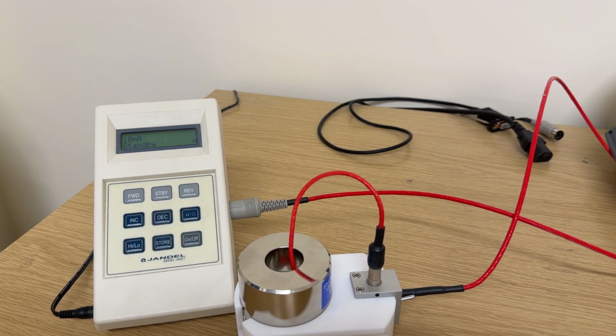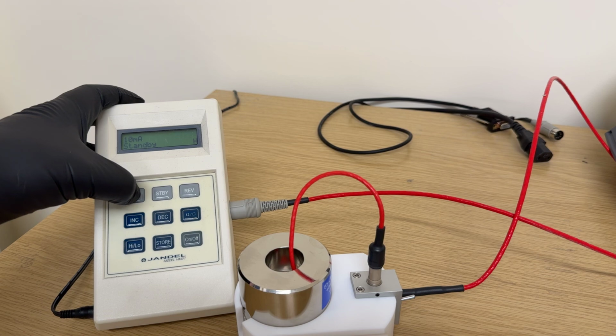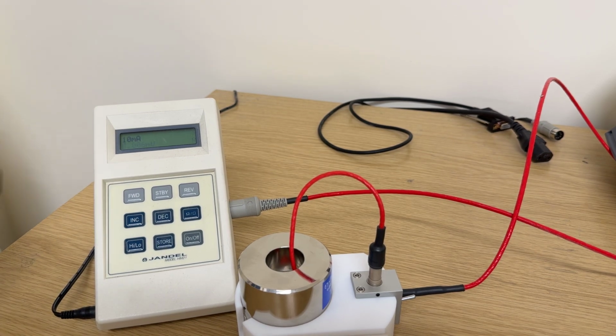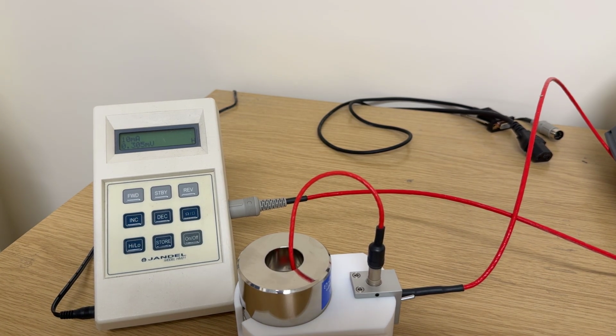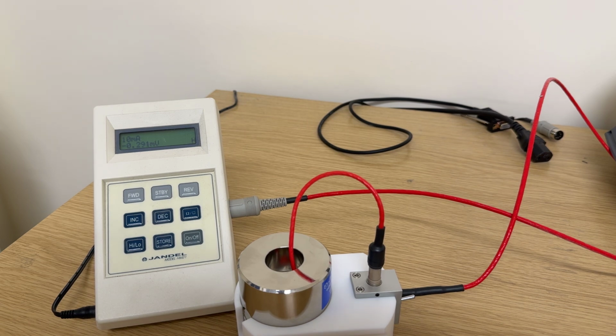And the HM21 here is on 10 milliamps, which is its highest current. We needed 100 milliamps really with the RM3000 Plus. So instead of getting 3 millivolts, we'll expect around 0.3 millivolts. So we're coming down towards the limits of measurement of the HM21. I'll pass the current in the forward direction. Then we're getting 0.304 millivolts. In the reverse direction, we're getting 0.291. Maybe they could match more closely.